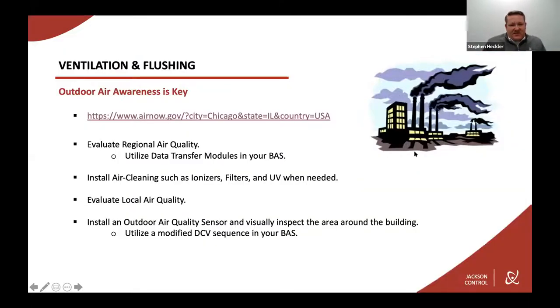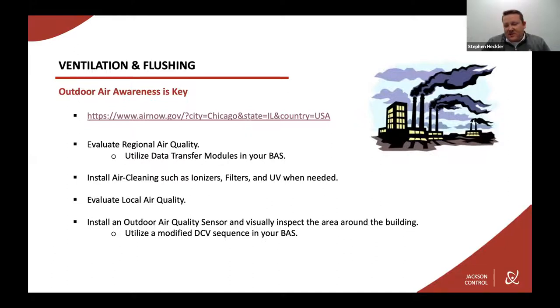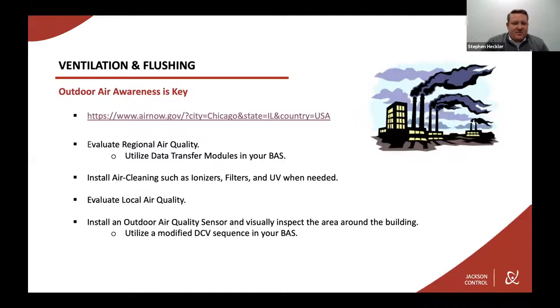If you don't connect to a site like that, you can install an outdoor air quality sensor. We have outdoor air sensors sensing temperature and humidity for enthalpy readings for demand control ventilation. You'd do similarly with an outdoor air quality sensor — looking at that outdoor air quality, comparing it to the indoor air quality, then deciding whether to bring in outside air and how much, or whether to increase your air changes per hour through the system.